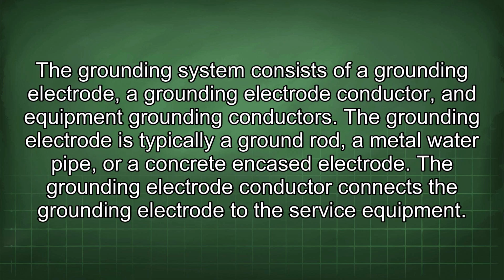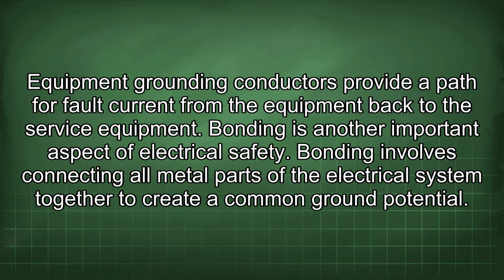The grounding system consists of a grounding electrode, grounding electrode conductor, and equipment grounding conductors. The grounding electrode is typically a ground rod, a metal water pipe, or a concrete encased electrode. The grounding electrode conductor connects the grounding electrode to the service equipment. Equipment grounding conductors provide a path for fault current from the equipment back to the service equipment. Bonding is another important aspect of electrical safety.